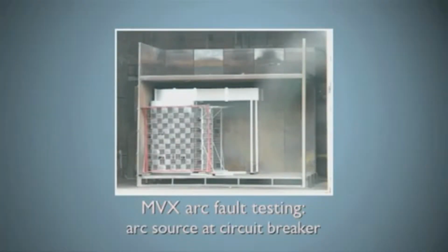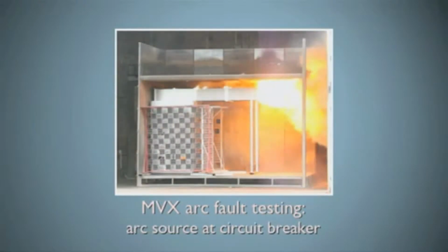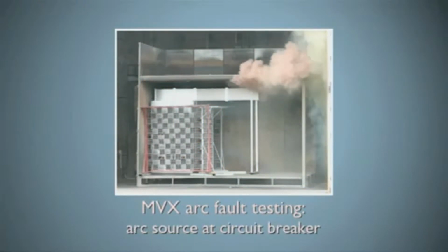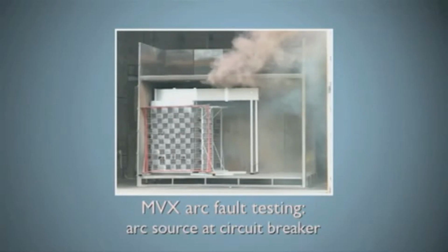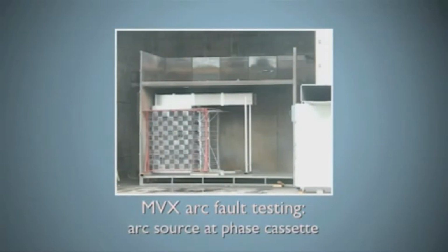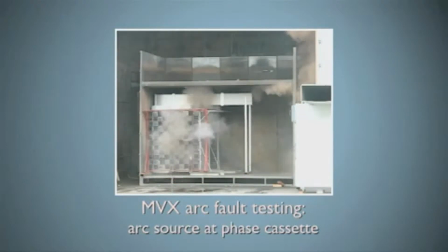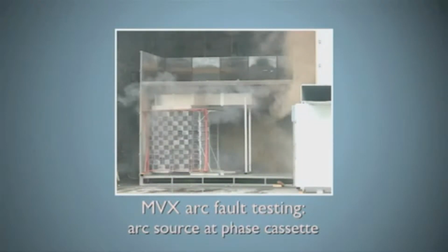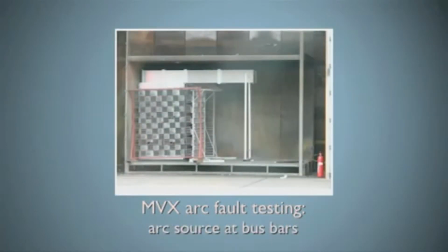This footage is arc fault testing of the MVX L series panels in a controlled environment. The panel is surrounded by cotton fabric on all sides to prove containment. If none of the material catches alight, the panel has passed the test. An arc event is deliberately caused in multiple locations inside the panel, at the circuit breaker, the phase cassette connection points, or at the bus bars.